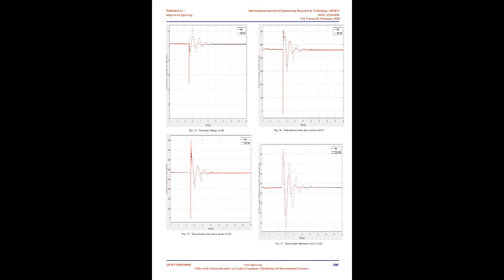The SVC can be operated in two different modes. In voltage regulation mode, the voltage is regulated within limits, and in VAR control mode, the SVC susceptance is kept constant. The block diagram of the control circuit is shown in Figure 5. Due to the use of reactive power feedback using a PI controller, it is possible to improve the transient response of the reactive power.